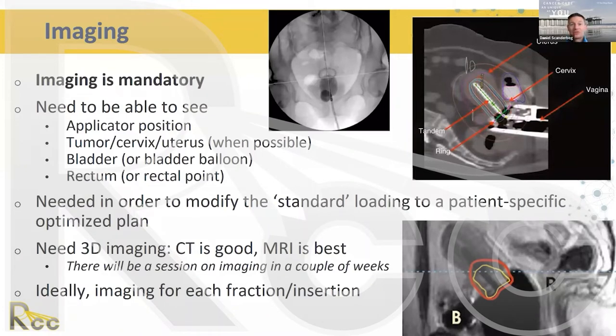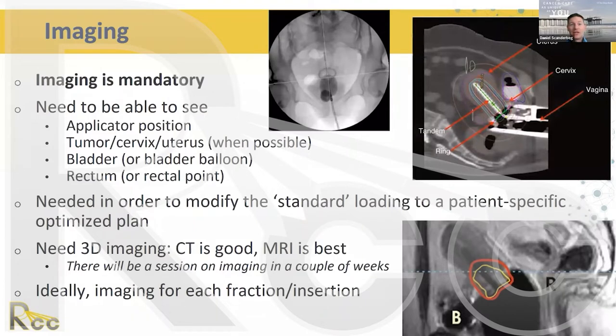Scanning parameters should be optimized as part of the commissioning process at the beginning of a new brachytherapy program and should be part of the radiation therapist's standard operating procedure. If the patient is going to be imaged outside the radiation oncology department, they should be accompanied by someone from the department who can ensure proper scanning parameters are used. The worst outcome would be returning with an image that can't be used because image quality is poor or the scan didn't extend far enough to capture all the applicator or target organs at risk.